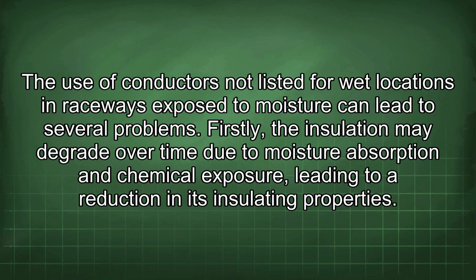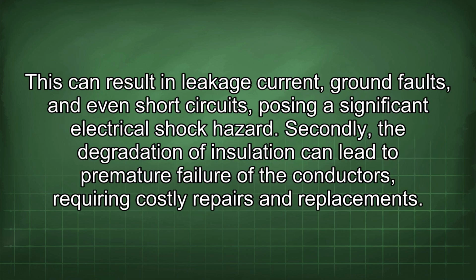The use of conductors not listed for wet locations in raceways exposed to moisture can lead to several problems. Firstly, the insulation may degrade over time due to moisture absorption and chemical exposure, leading to a reduction in its insulating properties. This can result in leakage current, ground faults, and even short circuits, posing a significant electrical shock hazard. Secondly, the degradation of insulation can lead to premature failure of the conductors, requiring costly repairs and replacement.